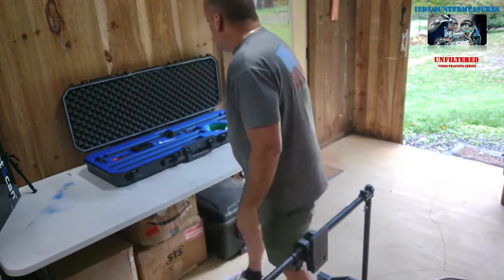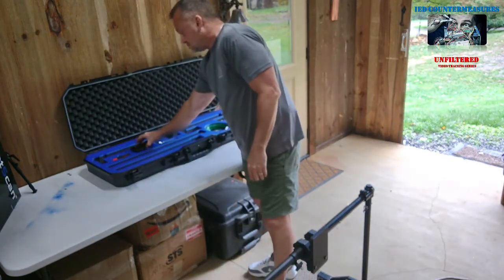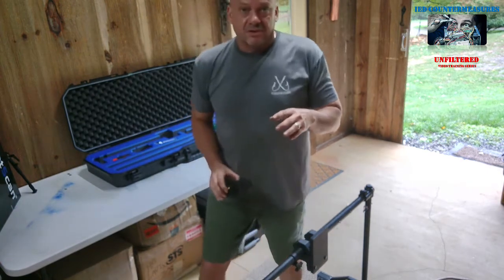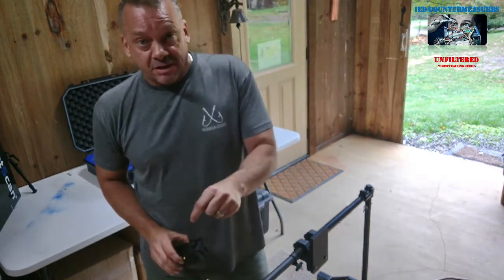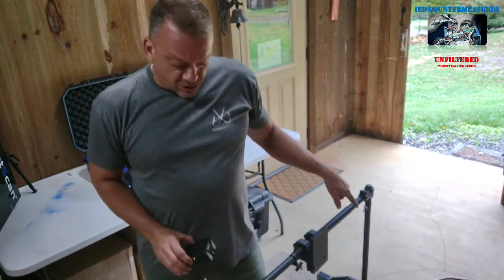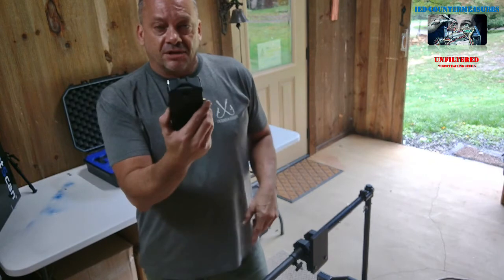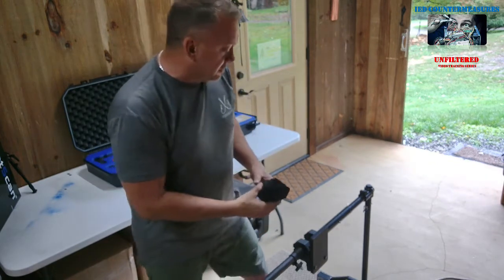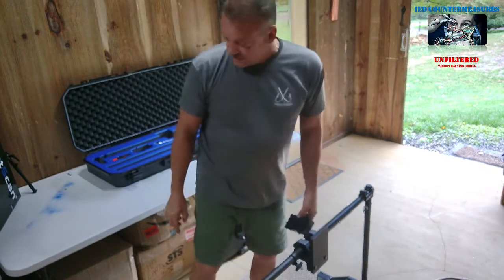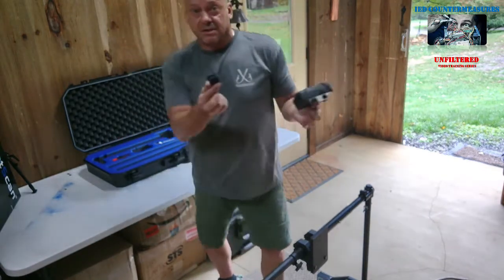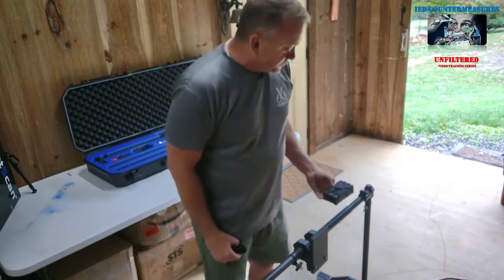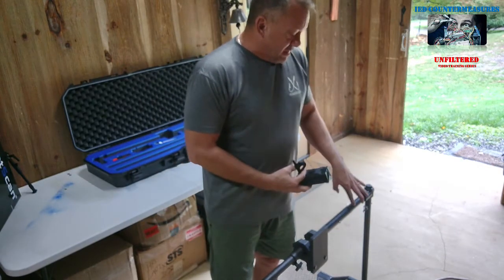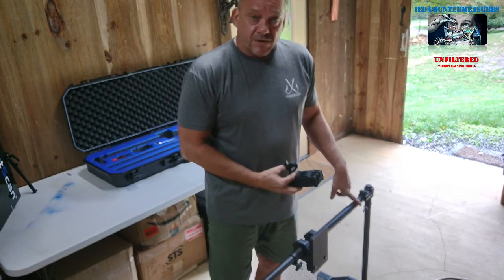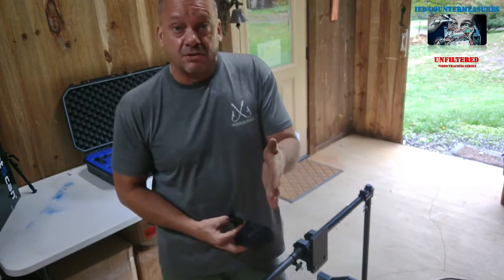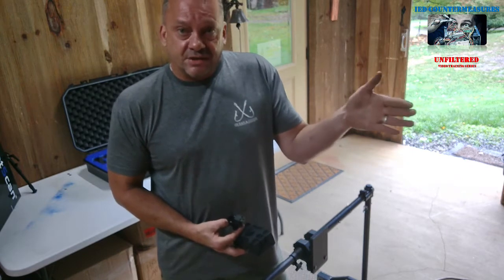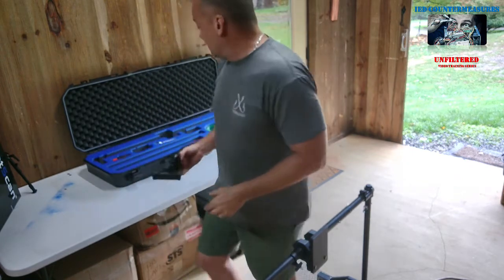Now, one issue with a C-arm is you may not have optimized imaging where your panel and generator are correctly aligned with the actual package. So this one has a built-in camera system running on 5.8 gigahertz. It can mount anywhere on the system using a simple mounting system—it just wraps and clicks in. I typically mount it right over my panel, since the panel gets closest to the actual package, so it lets you see exactly where it is from a downward view.